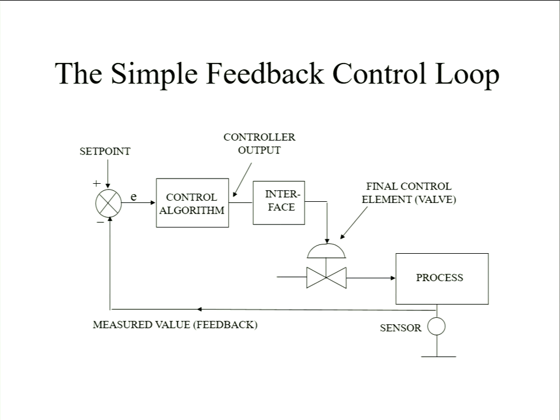How do we usually move the valves? Is it by electricity or? The majority need some form of electro-pneumatic translation. You'll find a 4 to 20 milliamp signal is quite a common electric signal to go around sites and plants. But then you're driving through, and it might be nitrogen, some form of pneumatic actuator. Some of the simplest control valves are actually more about force balance on a diaphragm, so it's a bit more implicit than this would show. But there's electromagnetic, what they call I2P controllers, current to pneumatic, and then you've got to have a think, what happens if I lose my current? Do I want to lose all my pressure? You can get them that are a bit like stepwise, so if they lose a signal, they'll hold their output. So you're often having to think of what happens if something fails, what's my next level of protection when you're designing the whole system.